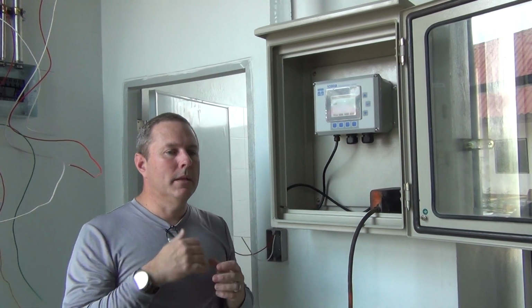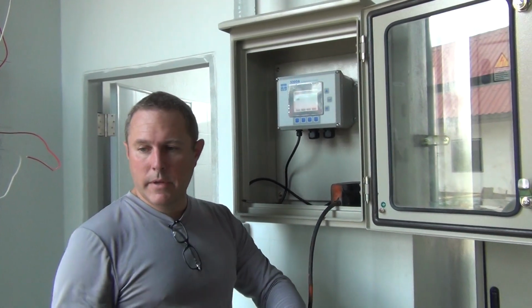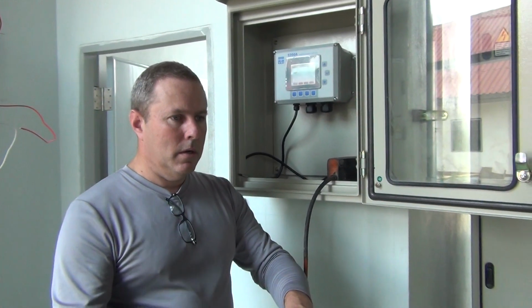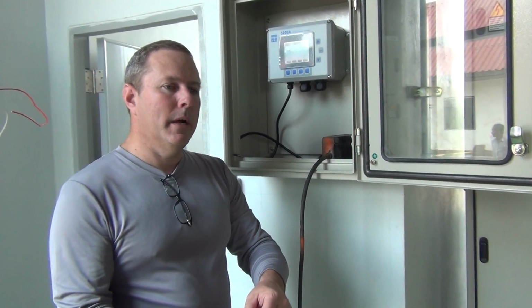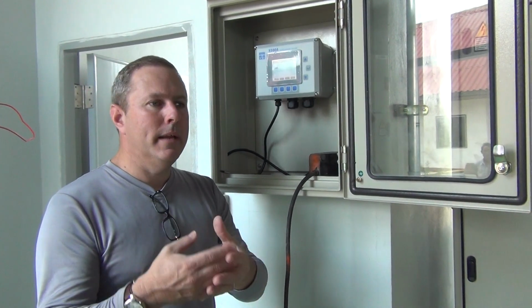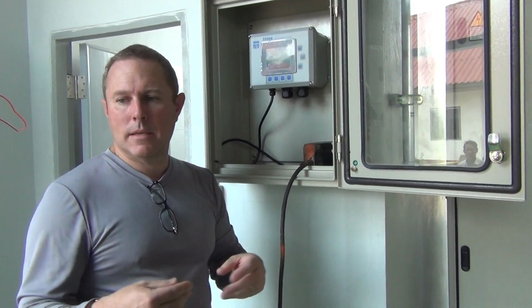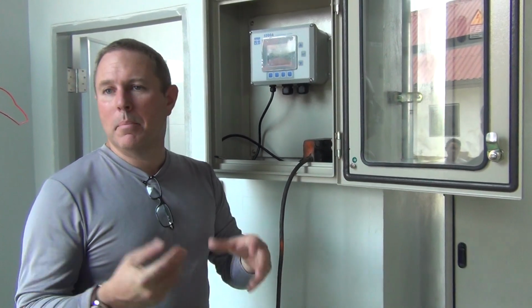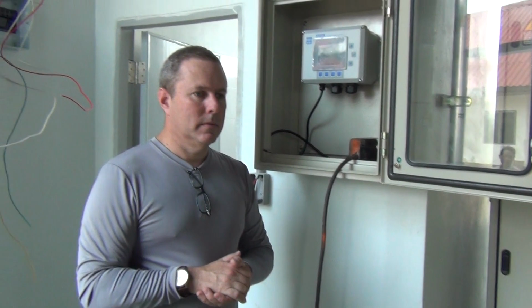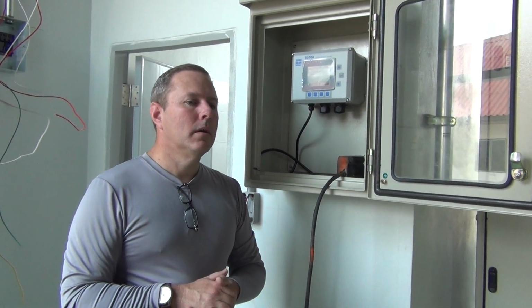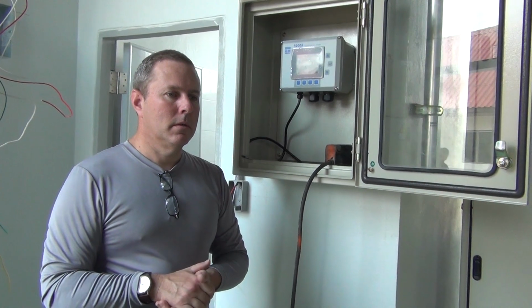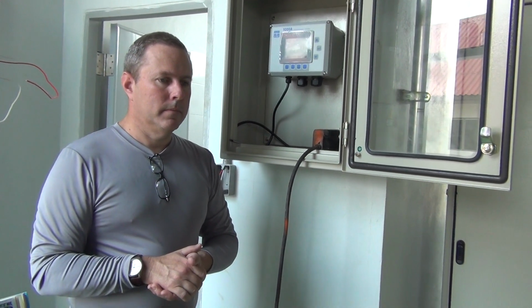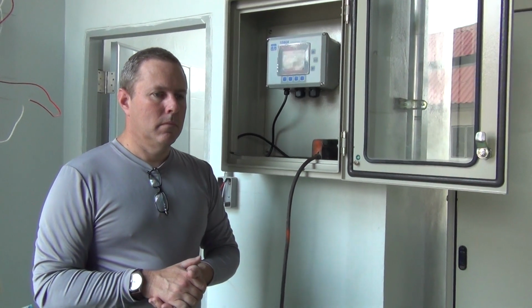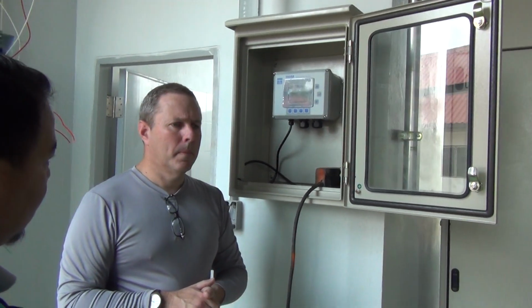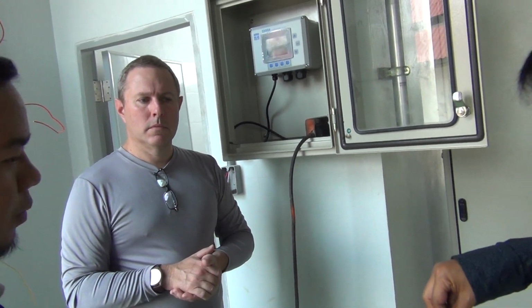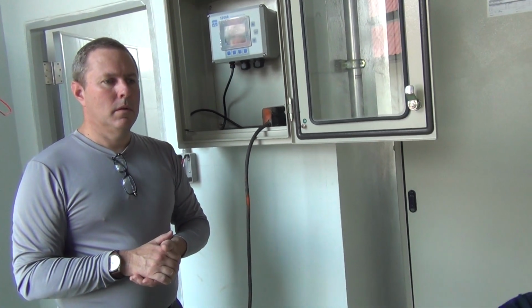To clean the probe, all you're going to do is remove the cover, take fresh clean water, and remove any accumulated biomass and debris. Make sure that there's no algae, diatoms, things like this on the probe. The probe can be fully submerged, but there should be no water entry. If the water level goes down, the probe is not in the water.